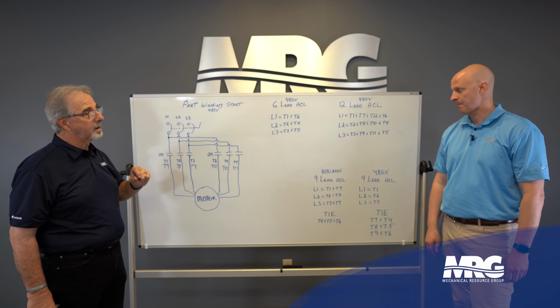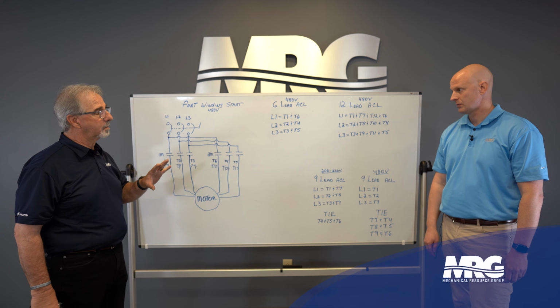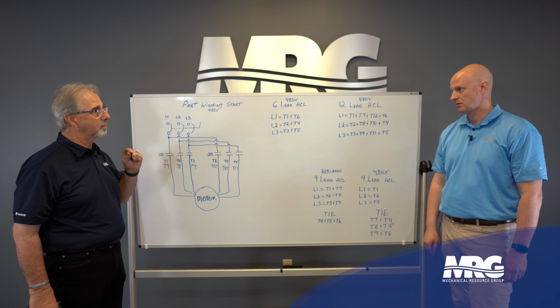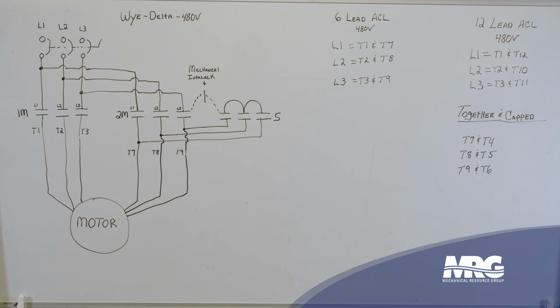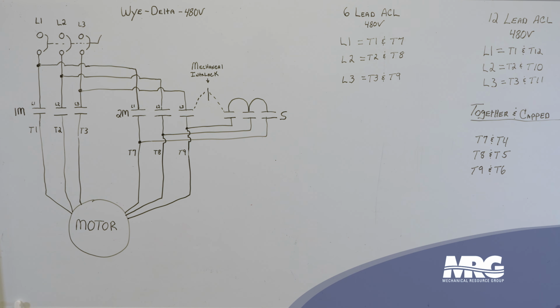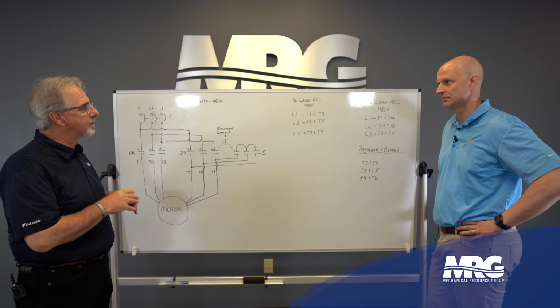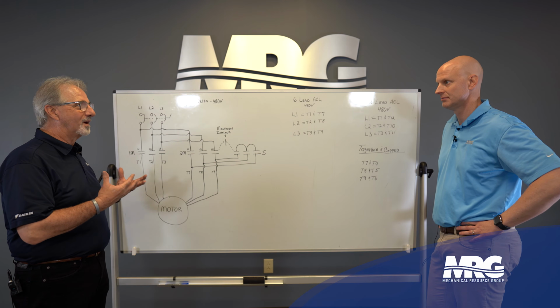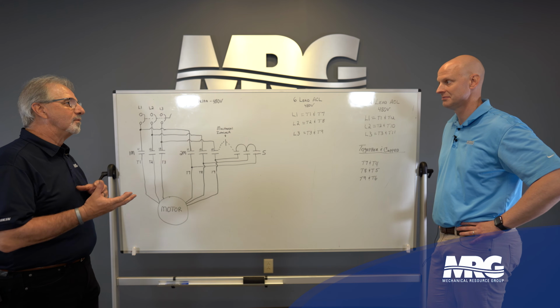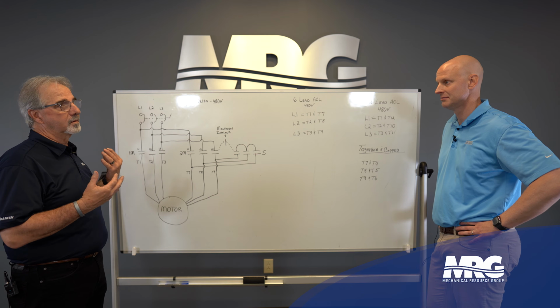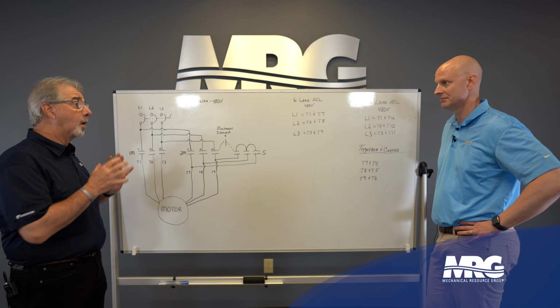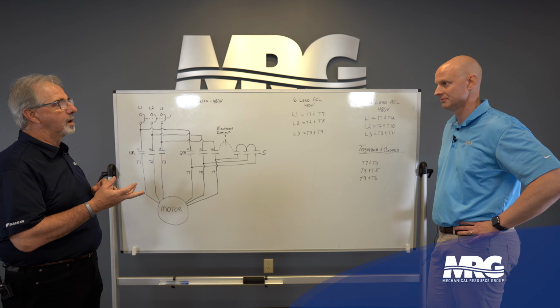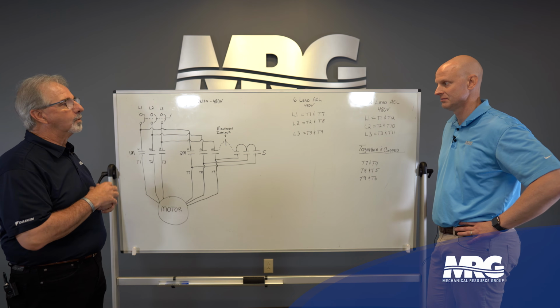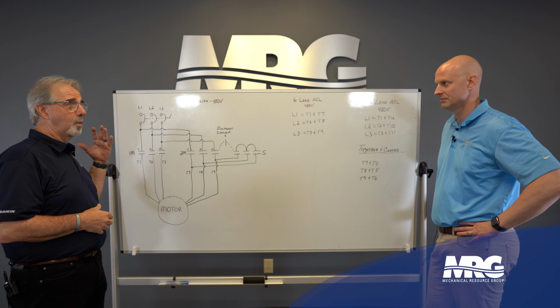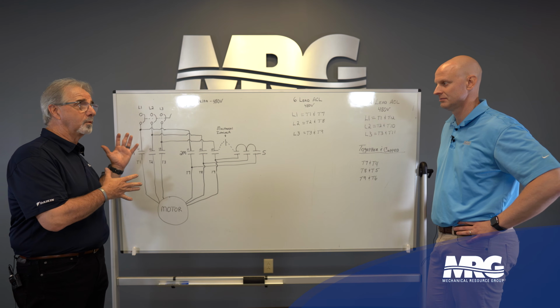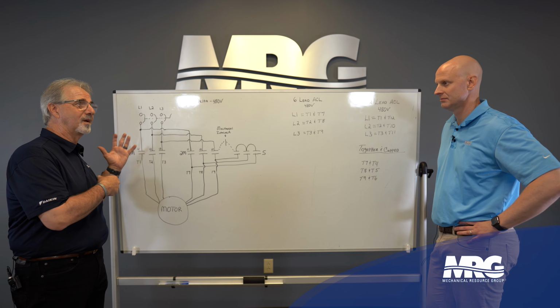So what we're going to talk about next is Wye-Delta, John, and the reason why I want to take a little bit of time on this one is this is the one that really causes a lot of issues in the field. Okay. All right, Wye-Delta. This one here is the one that really kind of scares you when you walk up to it. Now remember, in part winding start, we had a 2-contactor system. Well, when we do Wye-Delta open transition, it's a 3-contactor system, okay? And what we have to do is we have to start on the Y part of the winding. Remember before we were splitting it up 68%, I was only connecting one side.